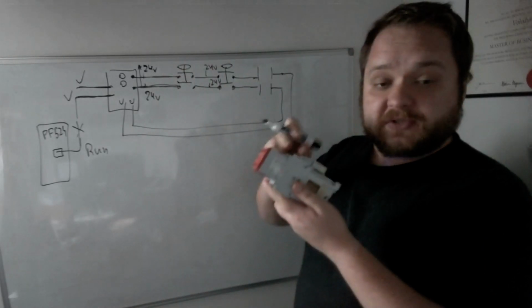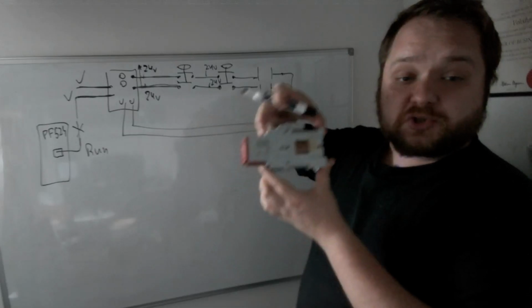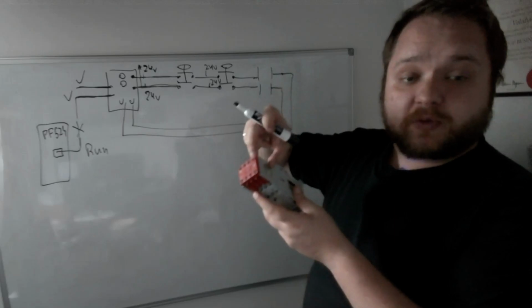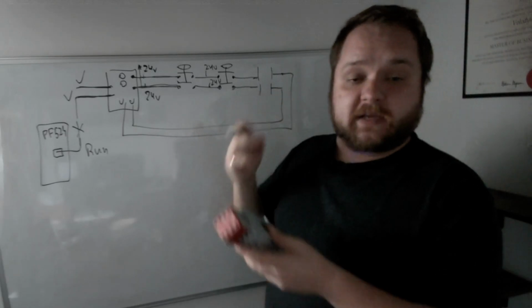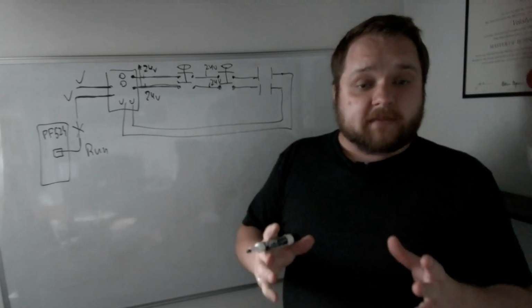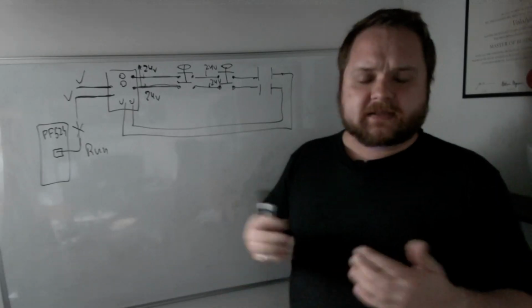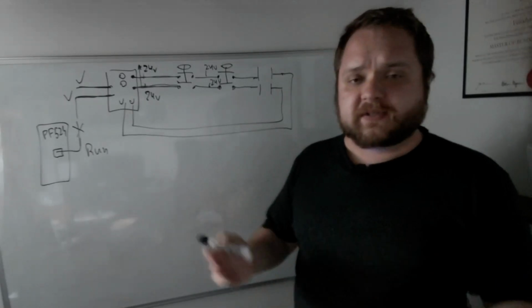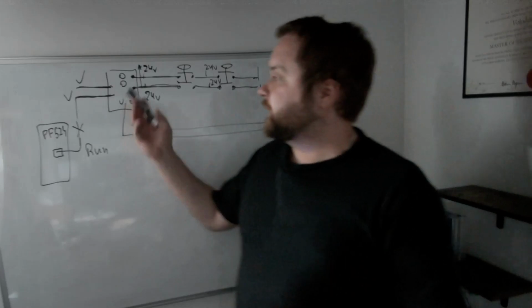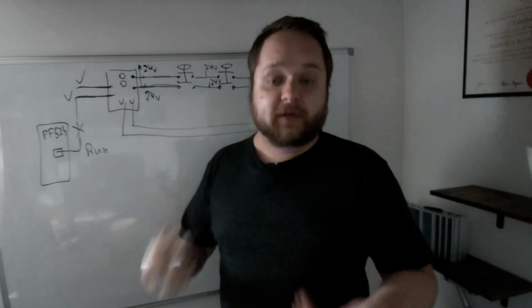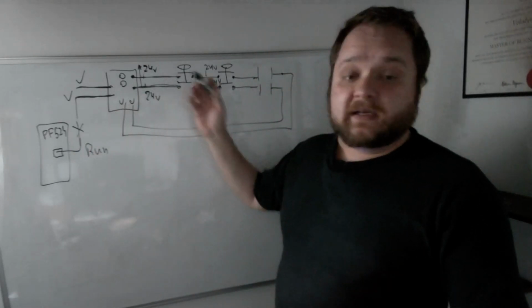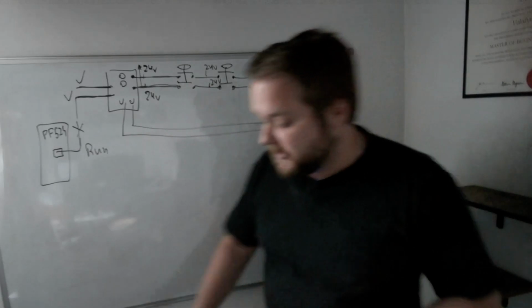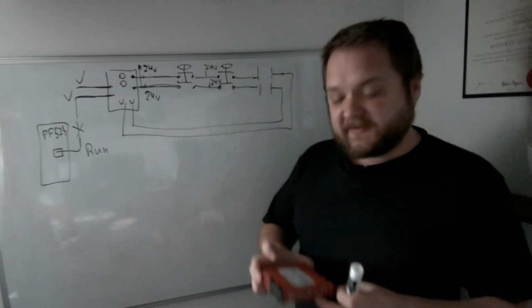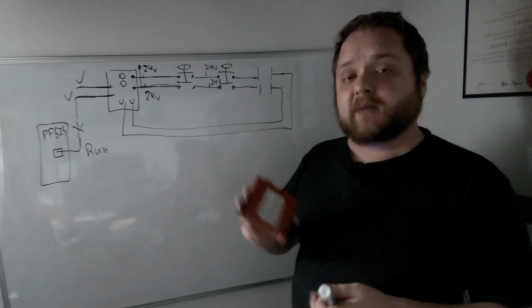So if we look at, for example, a contactor, you will notice that normally you have a much smaller device and footprint, but in this case, you have an add-on that is rated for safety. The same goes for your push button, and the same concept goes for everything. The technician or engineer or systems architect, it is definitely possible for you to create a normal ice cube relay system that would meet similar requirements. But remember that it needs to be rated for safety for you to consider that application safe.